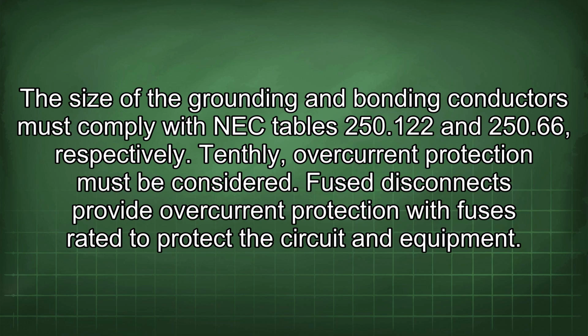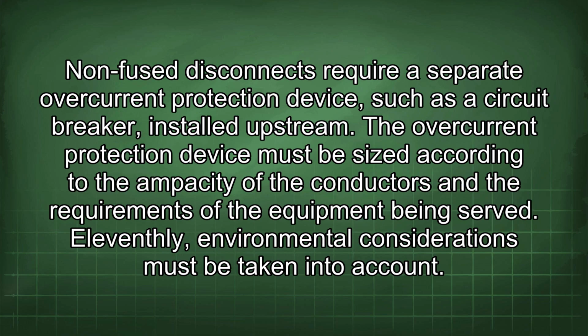Fused disconnects provide overcurrent protection with fuses rated to protect the circuit and equipment. Non-fused disconnects require a separate overcurrent protection device, such as a circuit breaker, installed upstream. The overcurrent protection device must be sized according to the ampacity of the conductors and the requirements of the equipment being served. 11thly, environmental considerations must be taken into account.